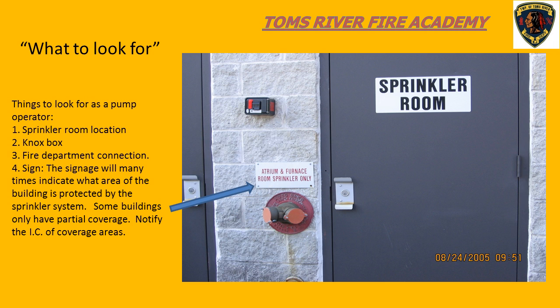This is a fire department connection, so you as the pump operator are going to be looking for the fire department connection. Connect up to that. You may see some signage above or near the fire department connection. It may tell you what areas of the building the sprinkler services. If you do see signage like this, you need to contact the incident commander and advise him that the building is not fully sprinklered, but only certain areas of the building are.